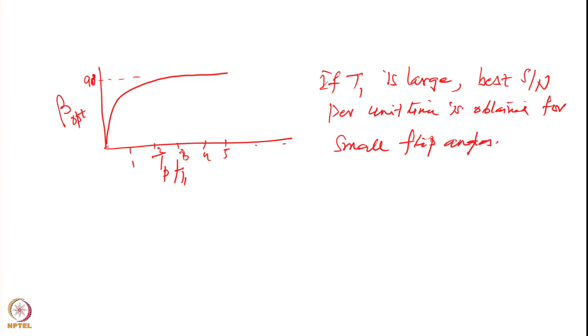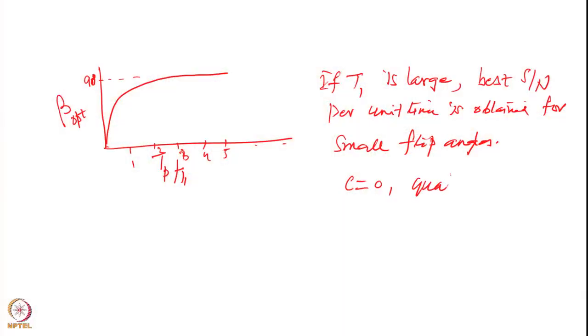This is typically the case for carbon-13. Carbon-13 relaxation times are very long. For example, carbonyl carbons have very long relaxation times because no proton is attached to them. Similarly, quaternary carbons have very long relaxation times. In such situations, if T₁ is large, the best signal-to-noise per unit time is obtained for small flip angles. We use a very small flip angle for carbonyls or quaternary carbons.